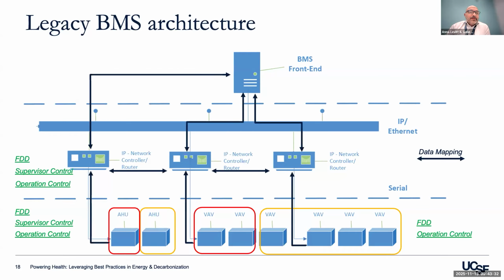So when you start mapping all this out, it begins to look like this, where you have to map up through the network controllers, pass data between them, down to the air handler, back up through the network controllers, and eventually this all gets integrated up into the BMS. This is a very common setup. It's very challenging when you're trying to maintain it, keep it going, make sure it works, and commission it—it becomes a very challenging architecture to maintain.